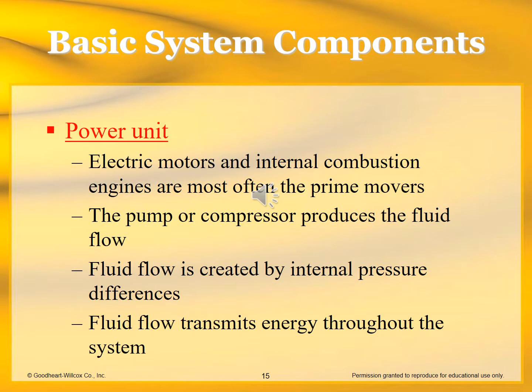Now the power unit. Again, the prime mover is the electric motor or the gas engine or diesel engine, and it turns the pump. Now the pump produces flow, not pressure. It produces flow. The flow inside the pump is actually created by squeezing the fluid. All right, so the fluid gets pushed into a void and gets squeezed out another direction. That's how flow is created. And we'll have some in the lab. I'll show you what we're talking about.